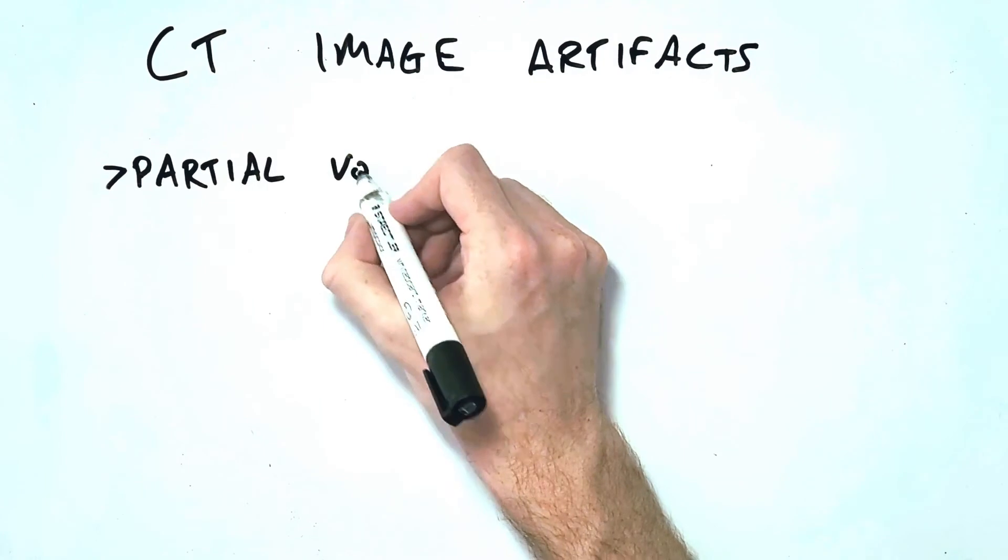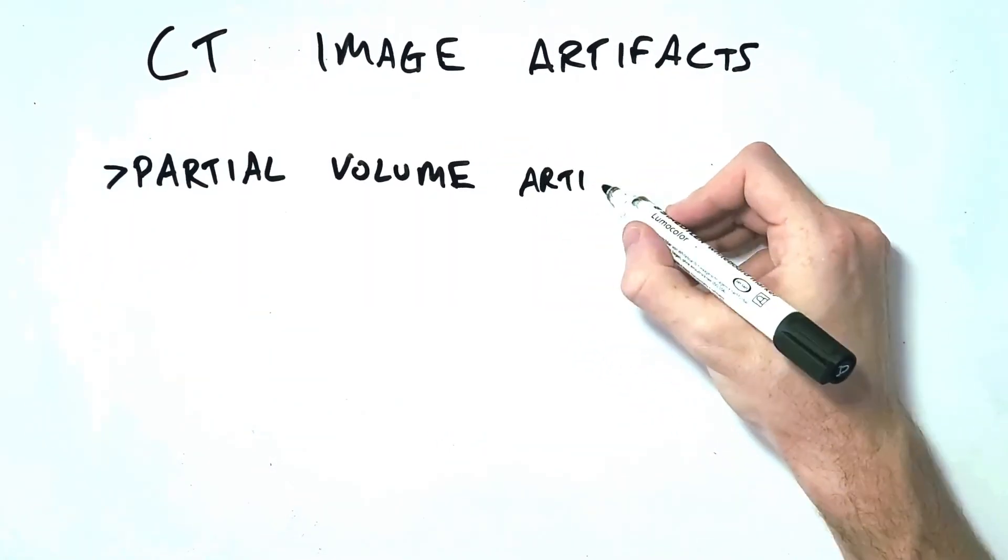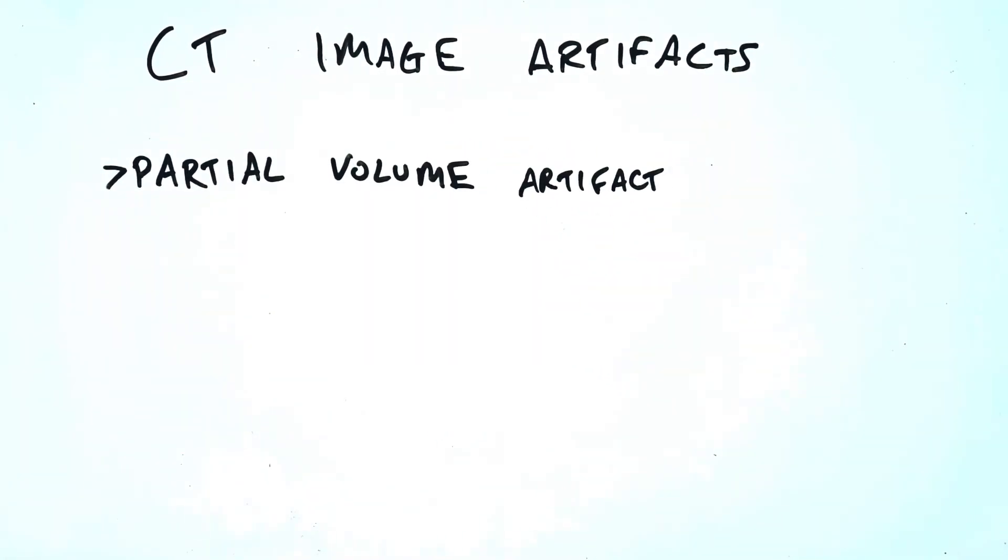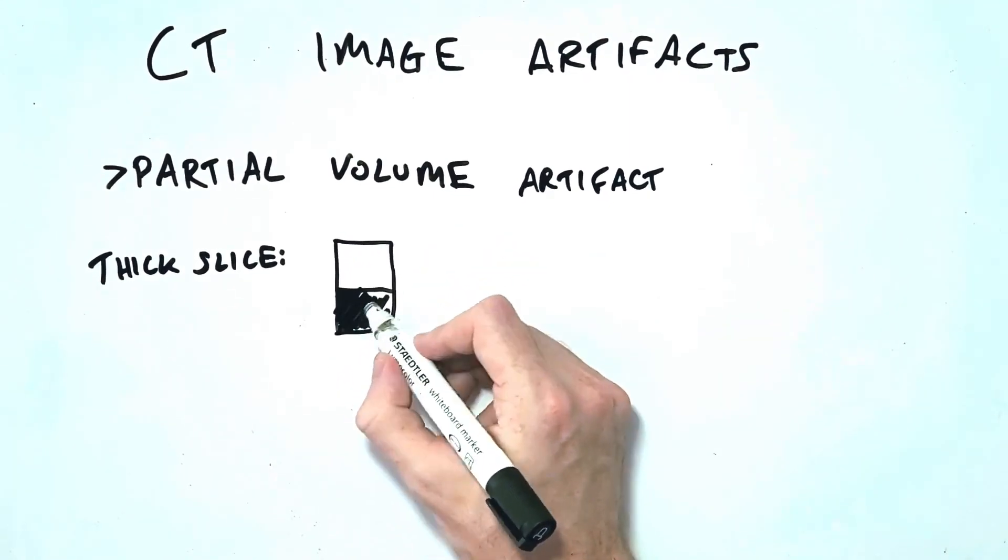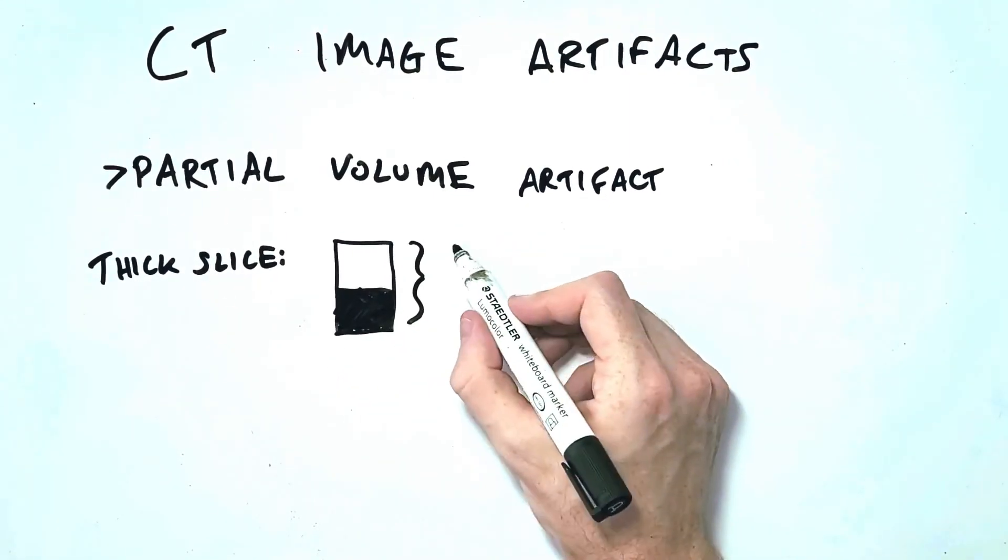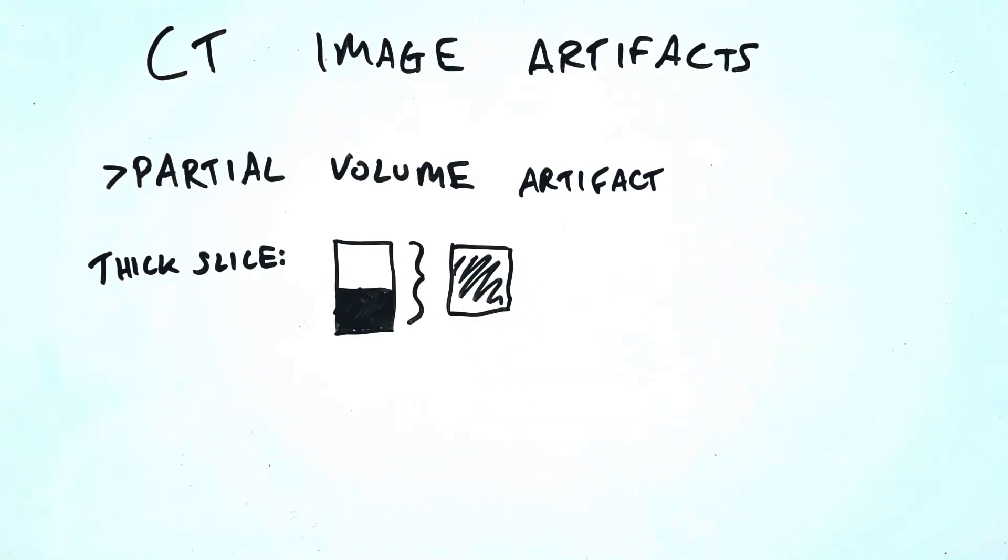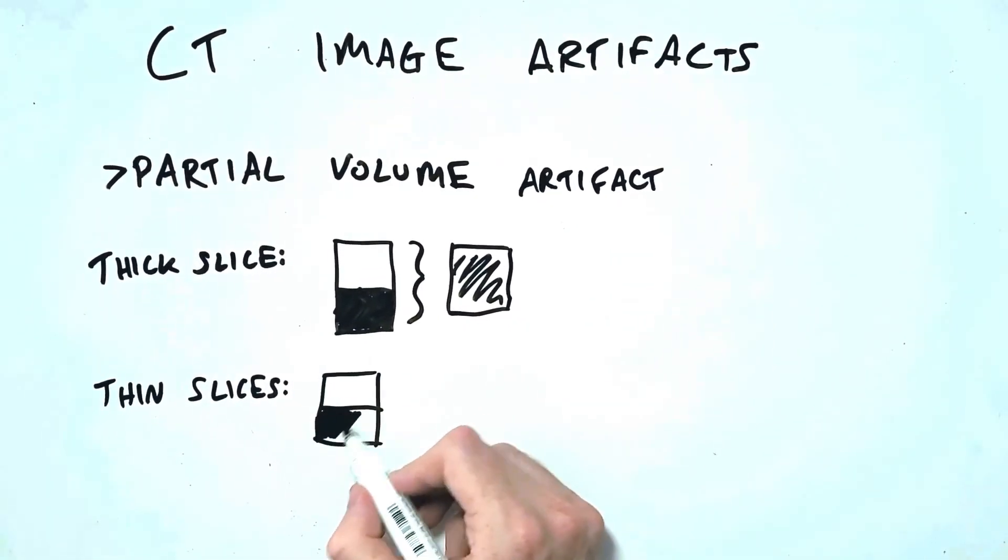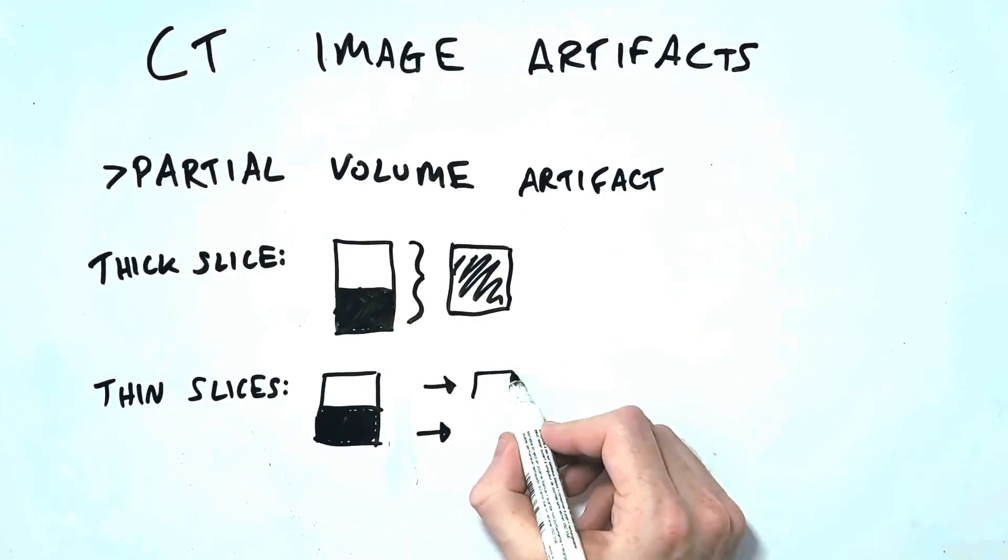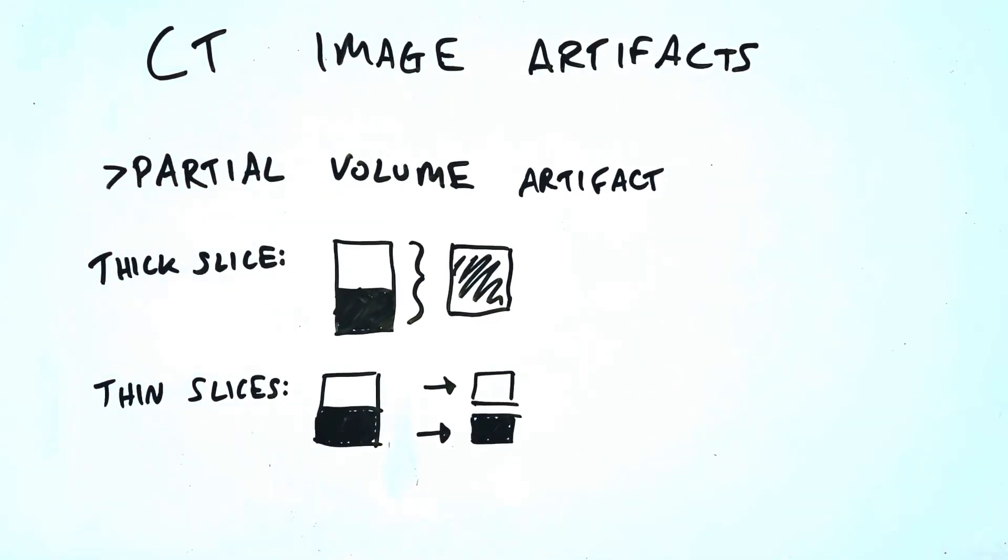Next up we have a partial volume artefact and this occurs when you have two structures of very different densities next to each other occupying the same voxel on a thick slice. If you have both black and white occupying the same voxel you will end up with an average grey, but that grey is not an accurate representation of what's actually happening in that voxel. We have black and white but we're seeing grey. The solution to this is to use thinner slices so that there's less volume being averaged within each slice.